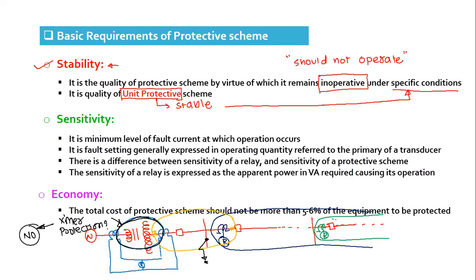Is it within its protection zone? Is this fault inside or outside the transformer's protection zone? What do you see? The fault on the bus bar, is it inside or outside the transformer protection zone? Yes, correct, Milan. It is not in the protection zone of the transformer, it is in the protection zone of the bus bar. We need to look at the bus bar relay for this.